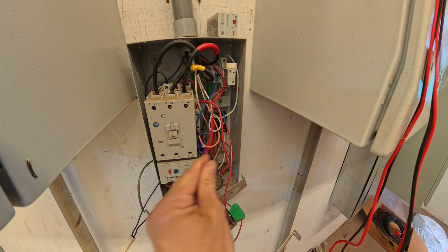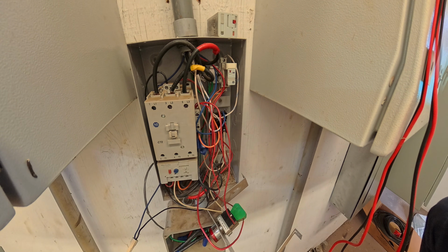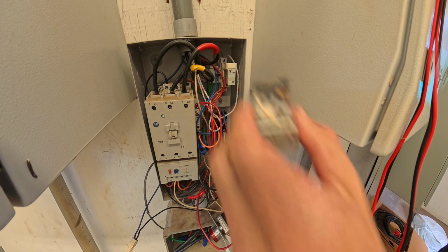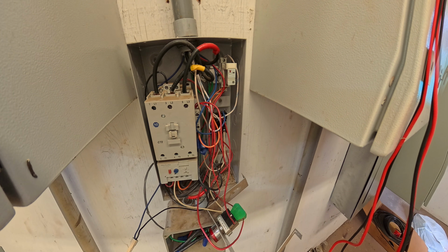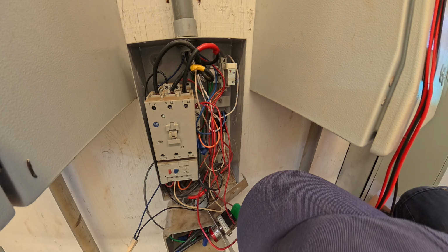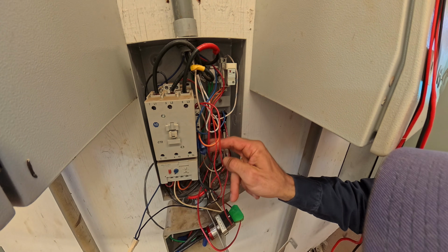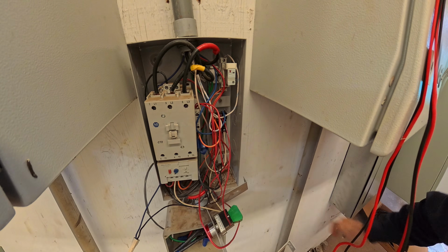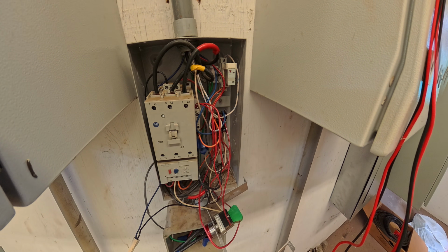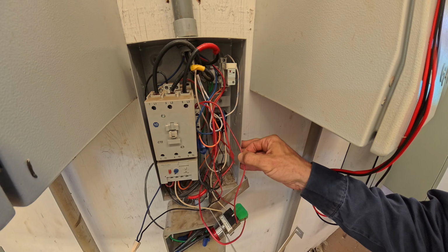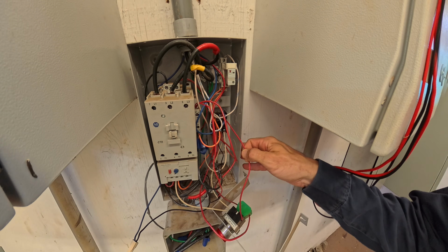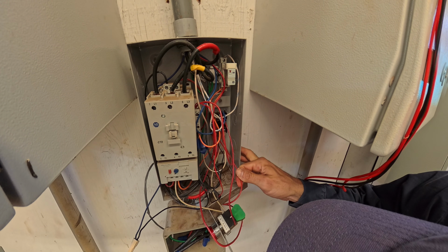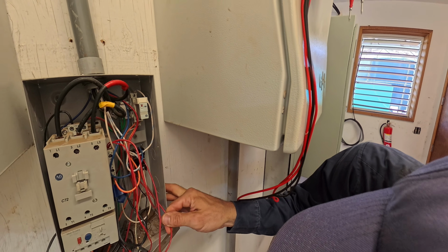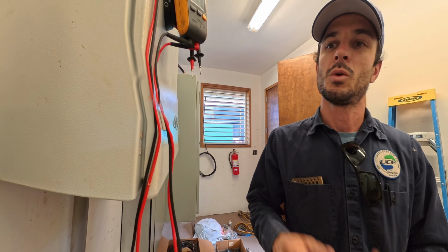This cable is the other end of their float switch. It is going on to 8 and it's getting a constant hot. Yeah, and then from 8 it's either going to 6 or 5 or both. There's 6. So from there it's going down and it's going to 7. So that's our coil, so that's what holds it true when it's true. And then the push button just shunts that out. Push button is also on 8. And so the float has to be true. The float has to be closed for the push button to work. Okay, perfect.